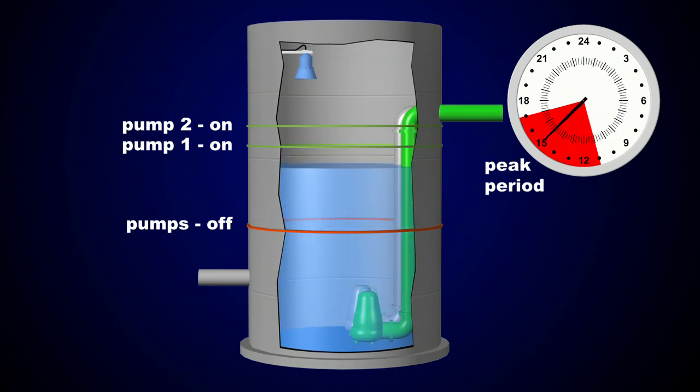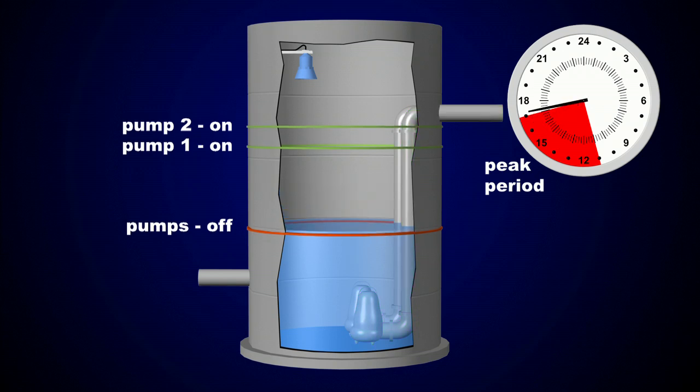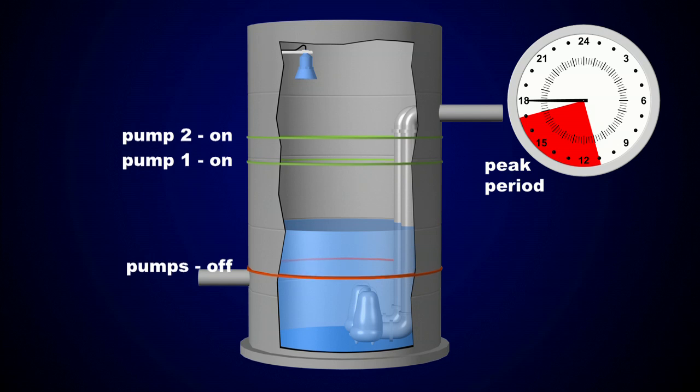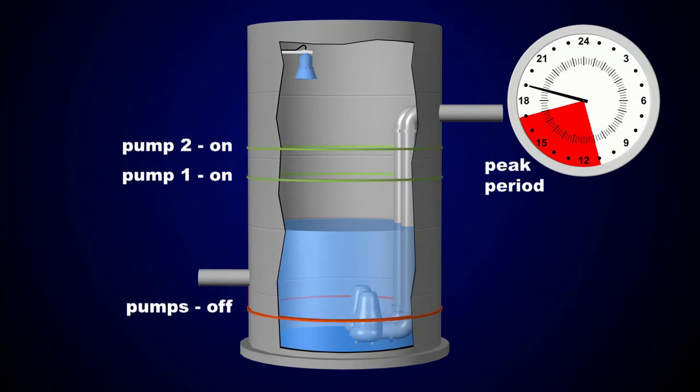During this peak tariff period, the pump run times will be shorter and less energy will be consumed. When the peak period ends, the pump set points return to the normal, off-peak settings.